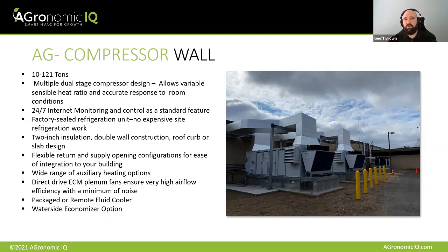So outdoor equipment from 10 to 121 tons. So small rooms or large, we would always recommend having multiple pieces of equipment per room, just for redundancy's sake. A minimum of 2 units per room is generally a good practice. Again, because each of those compressors is a two-stage compressor, in low speed, they're primarily sensible. That is the air conditioning piece. And in high speed, we add the latent back end, the dehumidification piece.